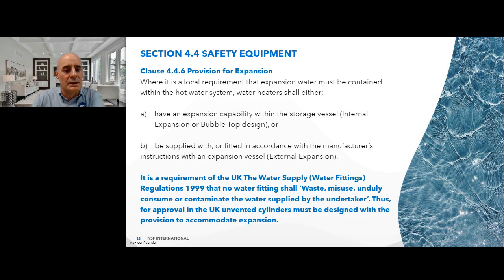It is a requirement of the UK Water Supply (Water Fittings) Regulations 1999 that no water fitting shall waste, misuse, unduly consume or contaminate the water supplied by the undertaker. Thus, for approval in the UK, unvented cylinders must be designed with provision to accommodate expansion.